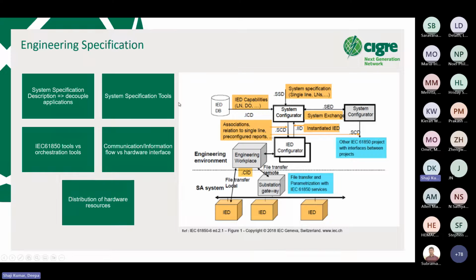Engineering is the very start of the system lifecycle. It starts with the specification phase and then moves into the commercial phase, where we request for quotation or conclude with contract signing. In this engineering phase, we use tools like system specification tools or system engineering tools as per 61850 standards. Functional requirements and associated performance criteria are to be documented in the basic application profiles in accordance with 61850, which is anticipated to offer machine-readable formats.